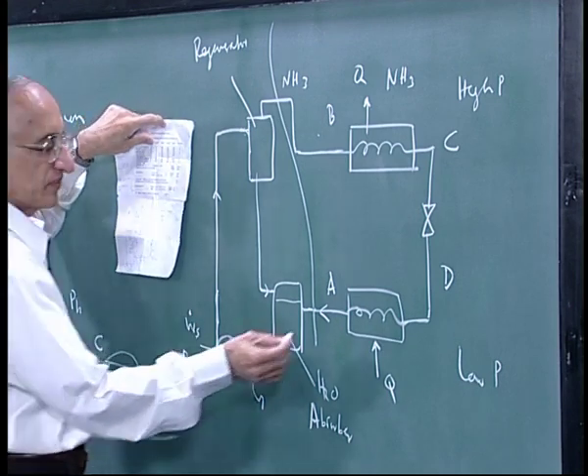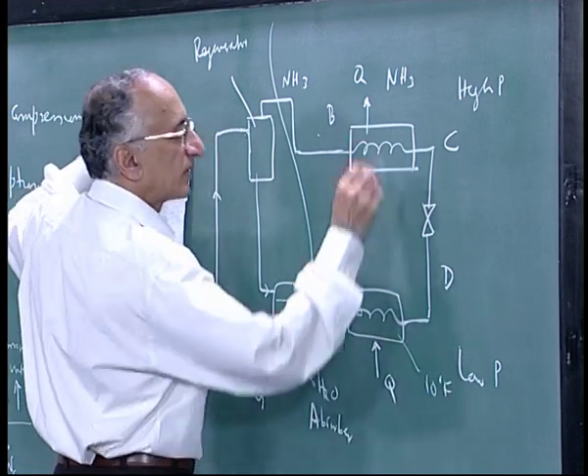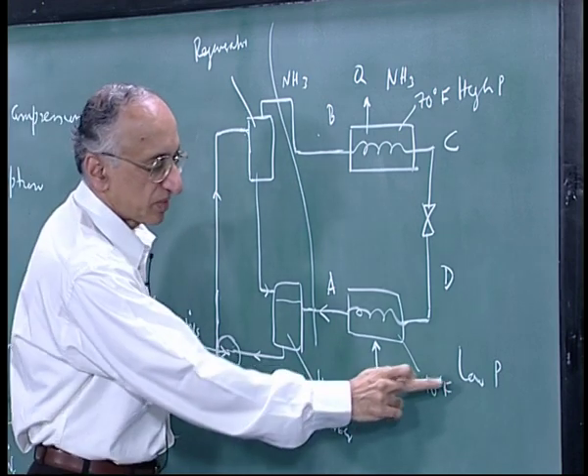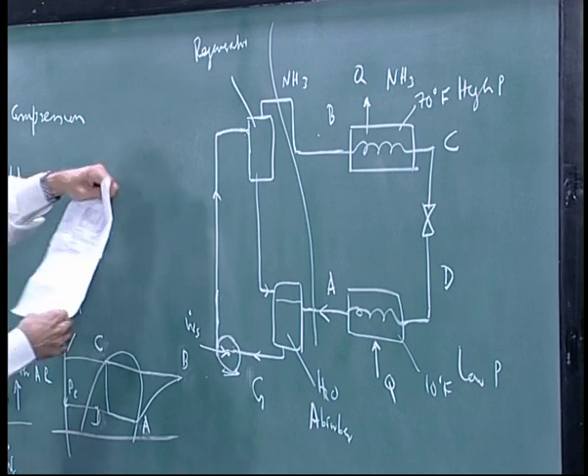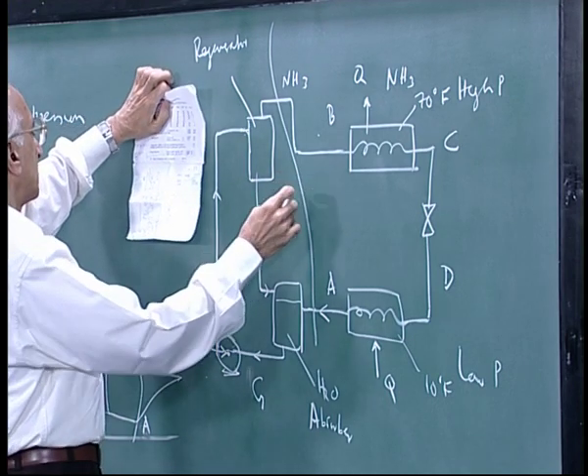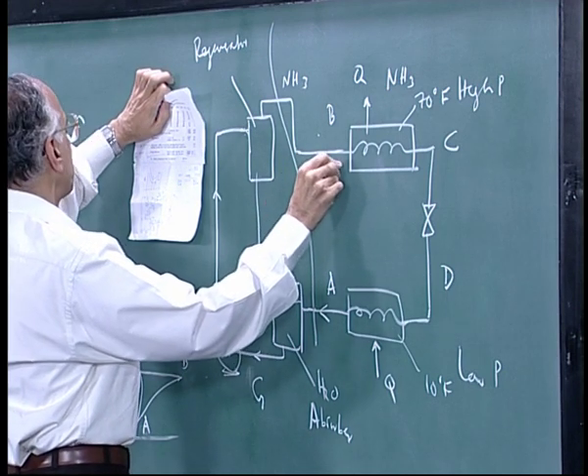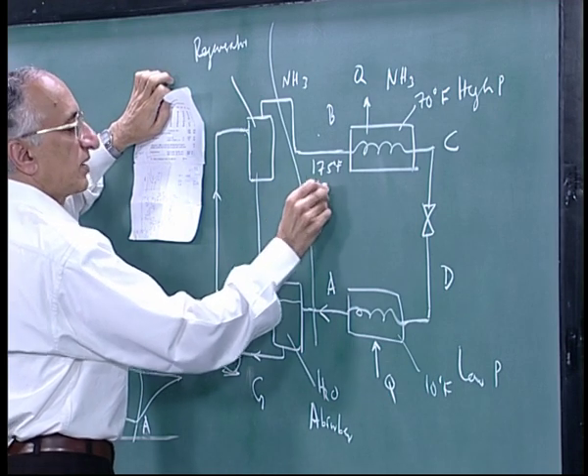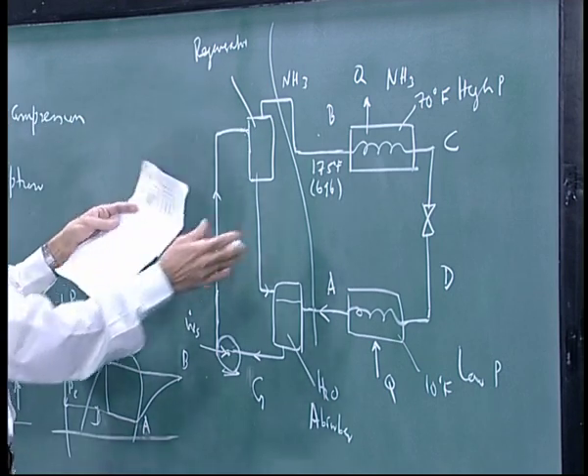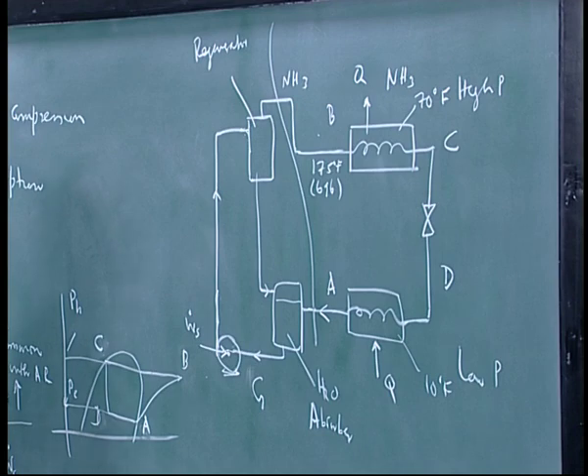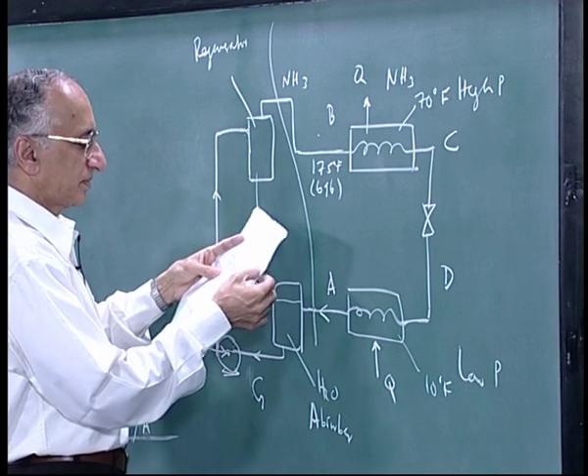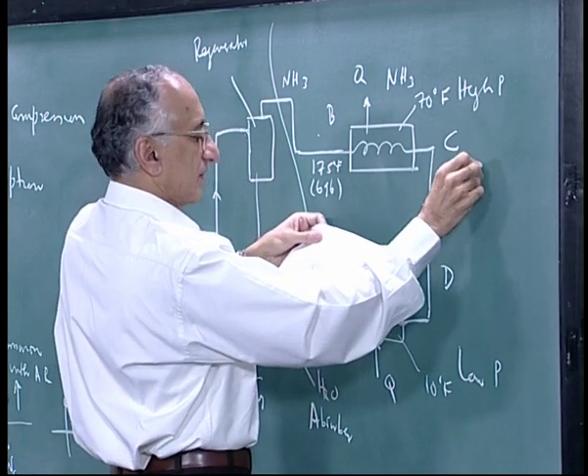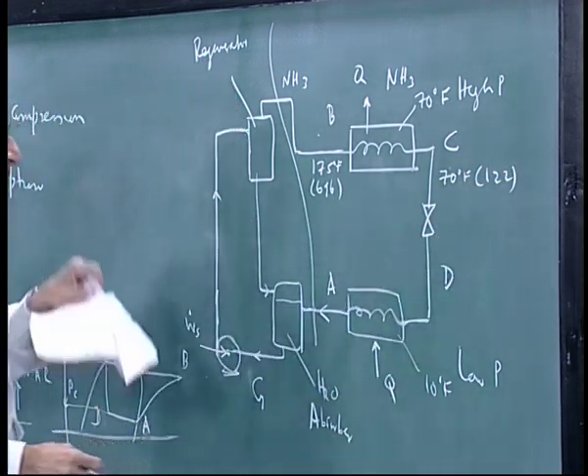This system works between 10 and 70 degrees F: the evaporator is at 10°F and the condenser is at 70°F. The corresponding high pressure is the saturation pressure of ammonia at 70°F, and the low pressure is the saturation pressure at 10°F. At the regenerator, the temperature is 175°F. All enthalpy values are in BTU per pound — the refrigeration industry still works primarily in British units.